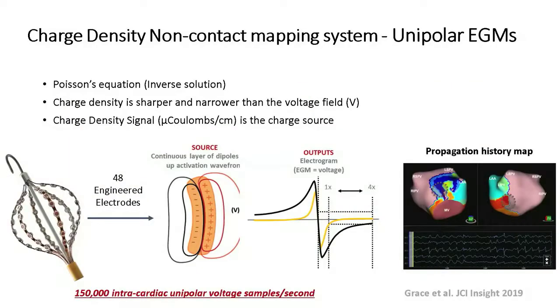This slide recaps some of the information already presented in this education series regarding the electrophysiological mapping capabilities, but it is worth revising for anyone in the audience unfamiliar with the technique. Electrical data is collected by the 48 engineered electrodes on the same catheter as the one I showed you on a previous slide, without making contact with the endocardium. This is the principle of non-contact mapping. The inverse solution equation has been changed to Poisson's equation to compute unipolar electrogram based on charge density, which mitigates the far-field component of the voltage-based electrogram.